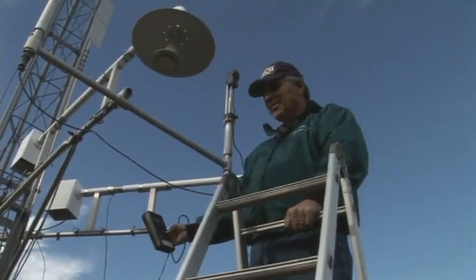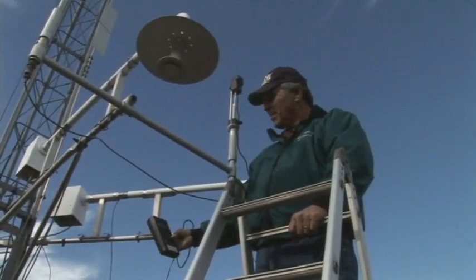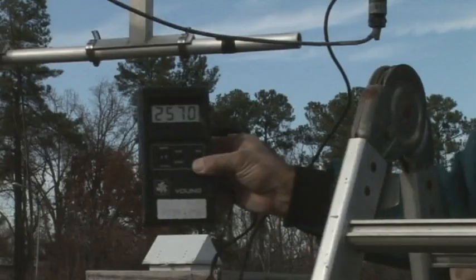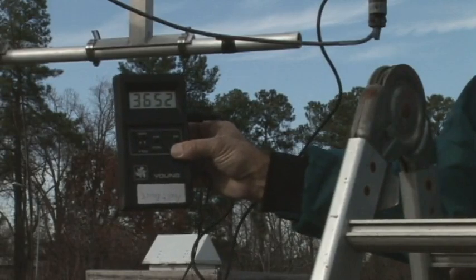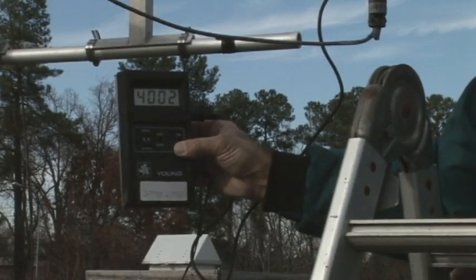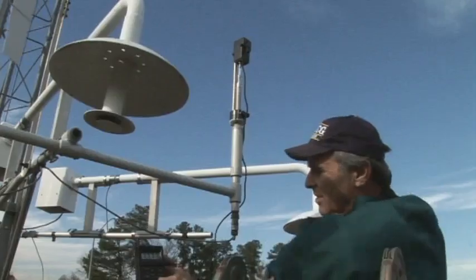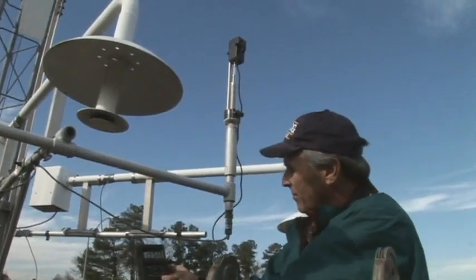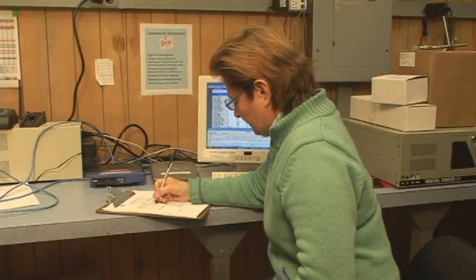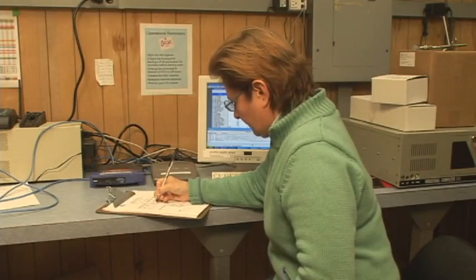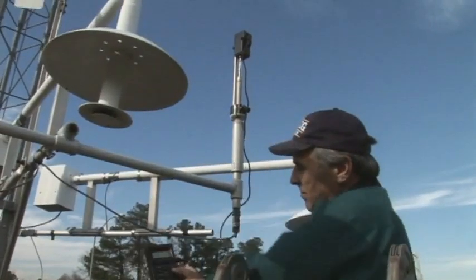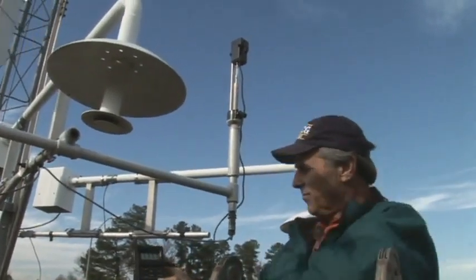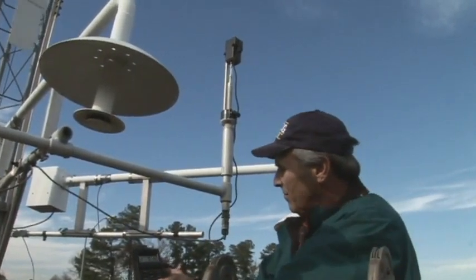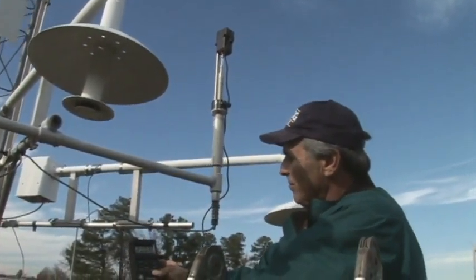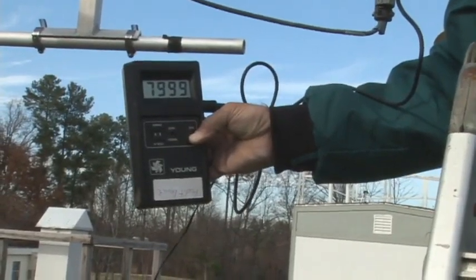Once the first value has been recorded, the outside technician must increase the speed of the motor to the second calibration point. This should be approximately 50% of the full-scale range. Once the controller shows that the speed has stabilized, the inside technician should record the response of the DAS. It is now time for the third and final upscale point. The outside technician will now increase the speed of the motor to 90% of the full-scale range.